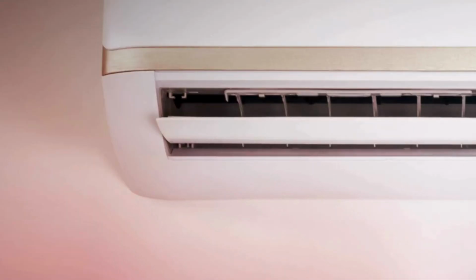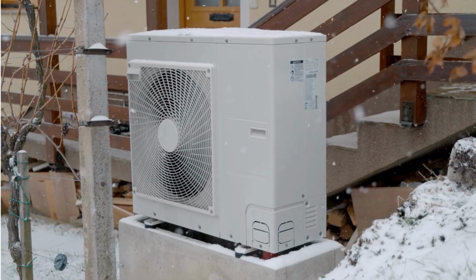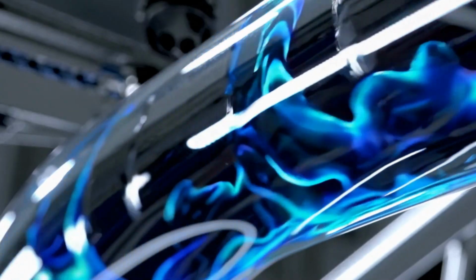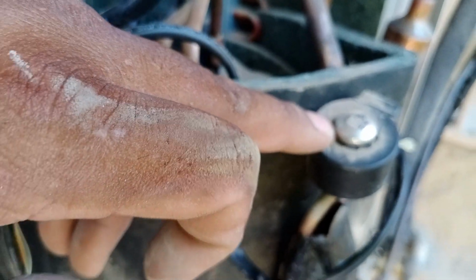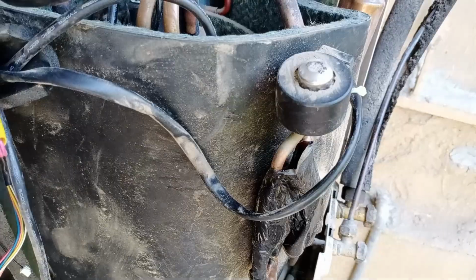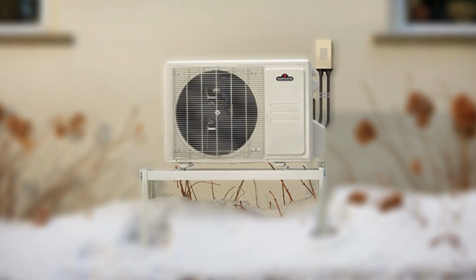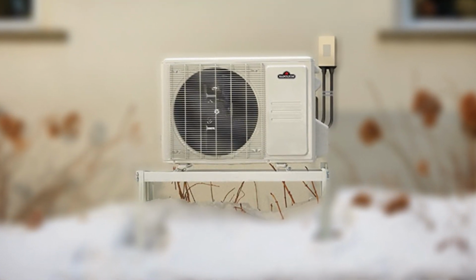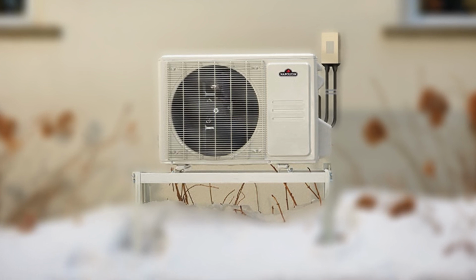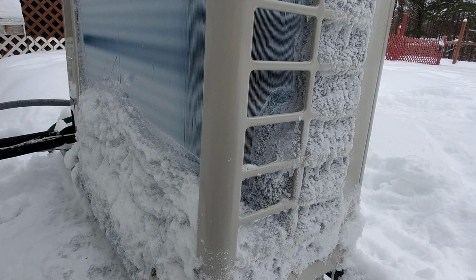The indoor unit is heating while the outdoor unit is cooling, essentially operating in reverse cycle mode. As refrigerant flows from the indoor unit to the outdoor unit, it passes through the expansion valve, which cools the heat exchanger. Since the outdoor temperature is already cold, the refrigerant passing through this section becomes even colder. This causes frost to start forming on the heat exchanger.